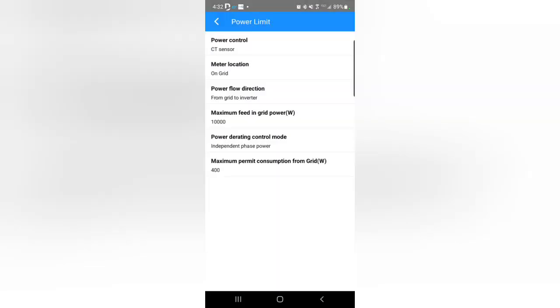So there you can set the max feed in to the grid. I have it on 10,000 on each of these. If you do it to like 6,000, it'd be 6,000 each for 12,000. So keep that in mind if you have any limits with the power company of how much you can back feed into the grid. If you don't want to feed any, you can put 0 there, and then it'll not feed any back to the grid if you have the CT sensors installed.